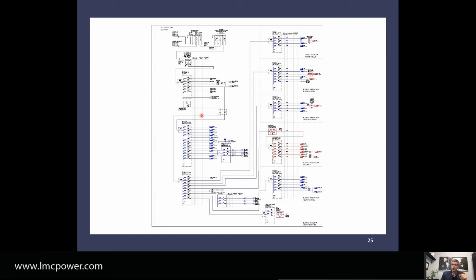Then from there it goes to two distribution panels, 1 and 2. This one has a very local presence, just protecting equipment right here, so we went with about 100 to 150 kA surge protector. Then we have another distribution panel where we recommended around 200 kA. Remember, category B could be 100 to 150, but if you have a lot of equipment connected, you might want to go a little higher if the cost permits - it's only $100, $200, $300 more. So they decided to go with 300, 200, 150 right here.